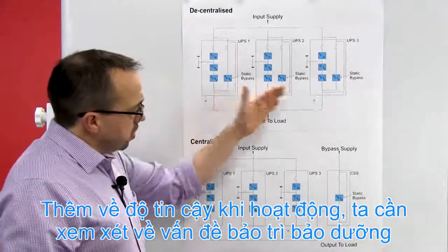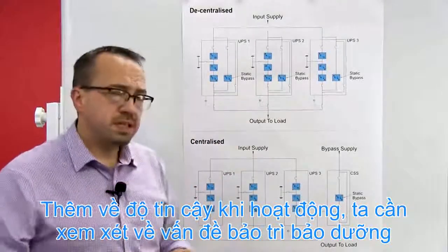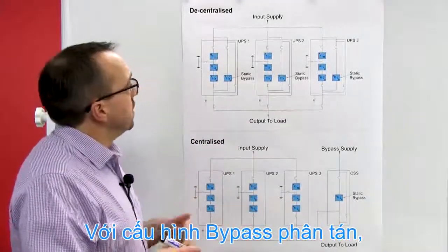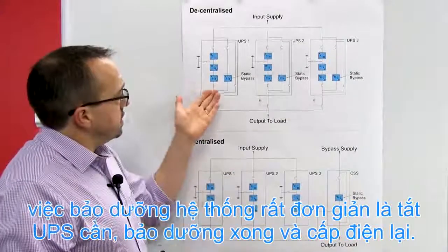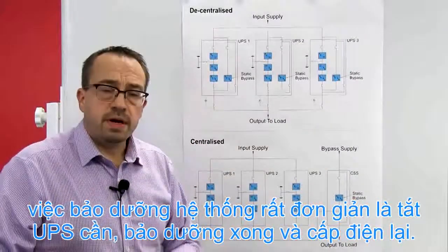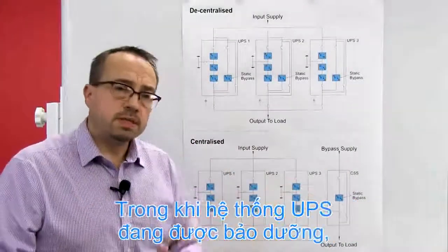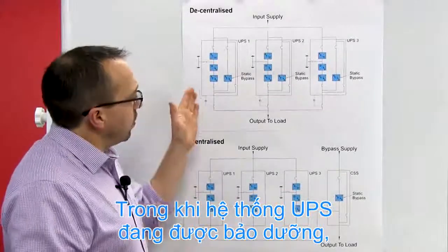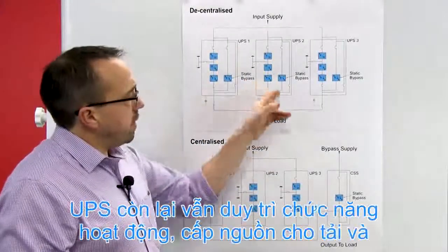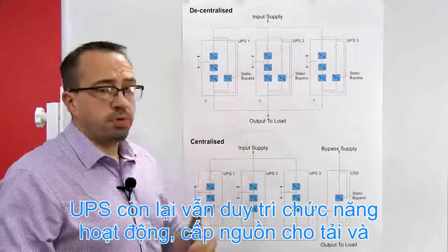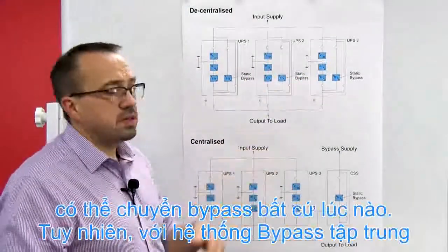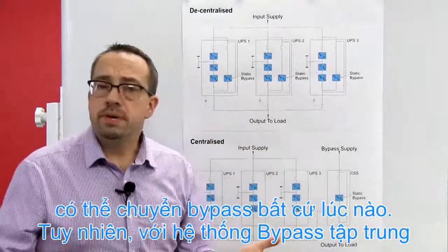In addition to the operation resilience, we've got to consider the maintenance resilience. With the decentralized system, if we need to maintain the UPS, we simply power down the UPS, maintain the UPS, and power the UPS system back on. However, whilst that UPS system is being maintained, the remaining operation module can still support the critical load and provide static bypass availability at all times.